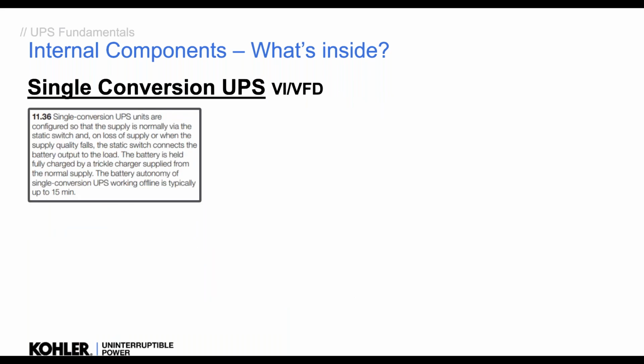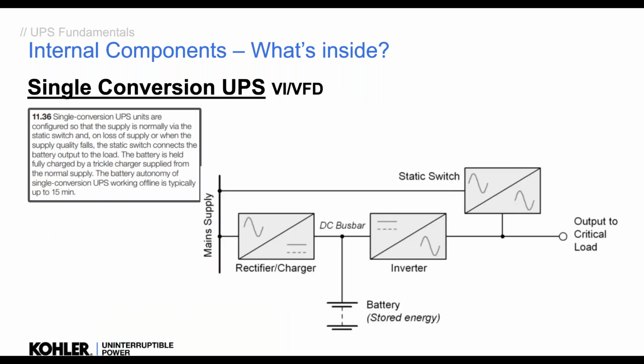So with a single conversion UPS, a VI or a VFD, these are offline UPSs. So what happens here is you have the mains, it's keeping the battery charged but not running on that, and that's normal. It's not running on inverter. It's typically running on this line, on mains out to the load, until the mains goes out of tolerance, and then the inverter switches on and feeds the load. So these are offline UPSs.